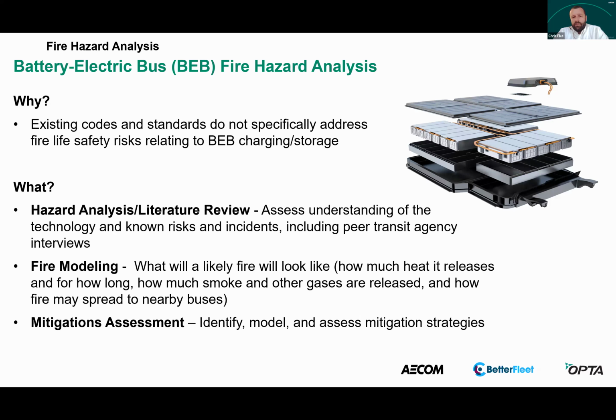But while BEBs are not stationary systems, the guidelines outlined by these committees can be evaluated for guidance on potential mitigations. Also, standards like UL 9540 and 9540A are helpful to understand what testing and evaluation options are available for energy storage systems. So when we're left with gaps in outlining the minimum requirements in adopting codes and standards, we start to look at performance-based design approaches in determining the minimum level of safety to achieve the safety goals for the different stakeholders that are involved.